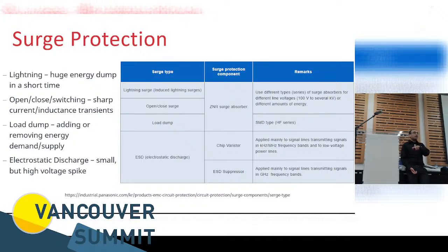The flip side to that is, because you've got so little resistance, you automatically become a magnet for all sorts of surge. So any sort of generator you've got in the house, it could be a gas generator like a Generac, or an inverter, these are all sources. All sources inherently are required to have very little internal impedance. Because they have very little internal impedance, you are a surge magnet. Which means it becomes even more important to protect yourself against surge, and you have to protect yourself against surge from different sources.